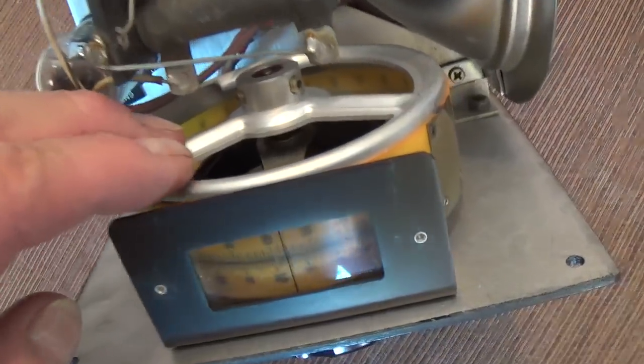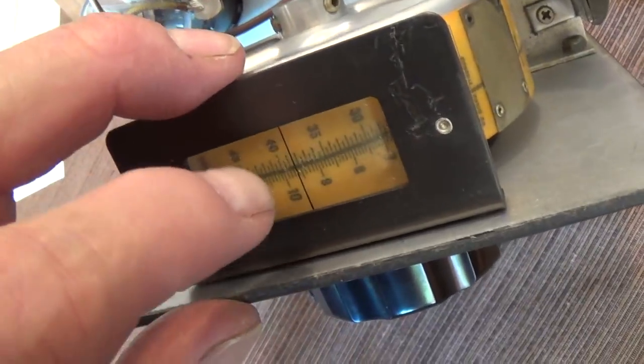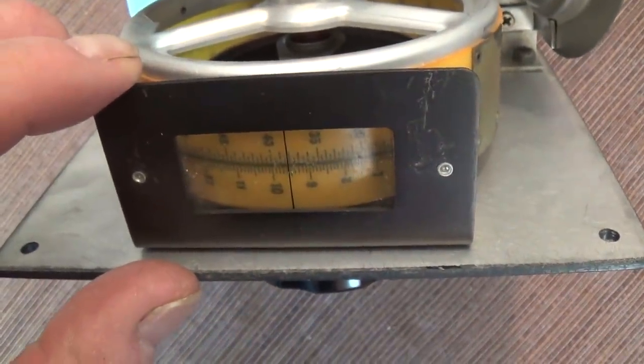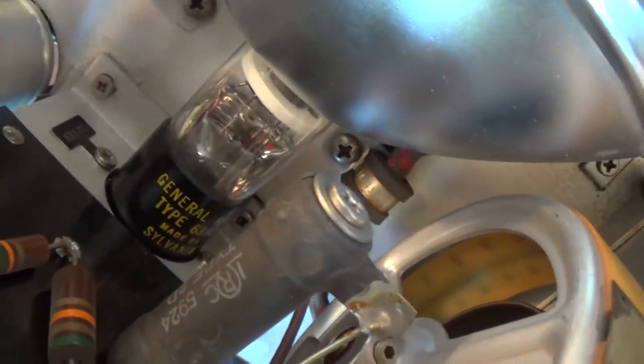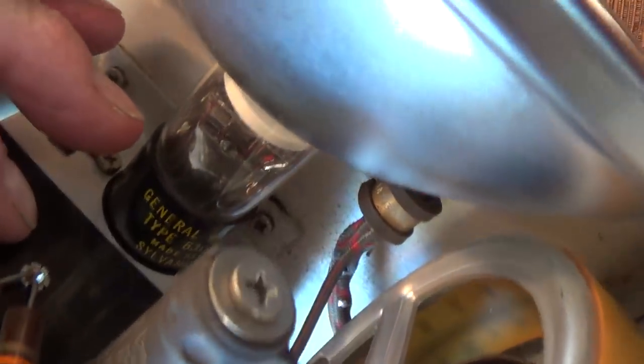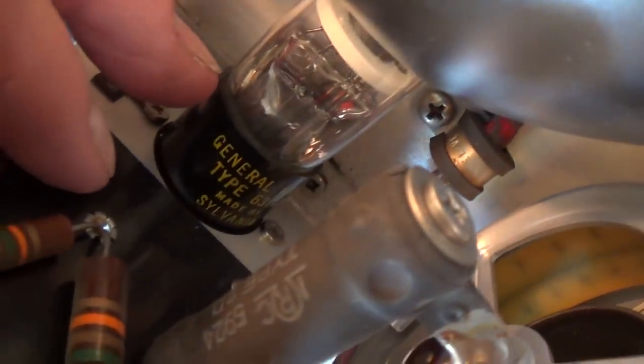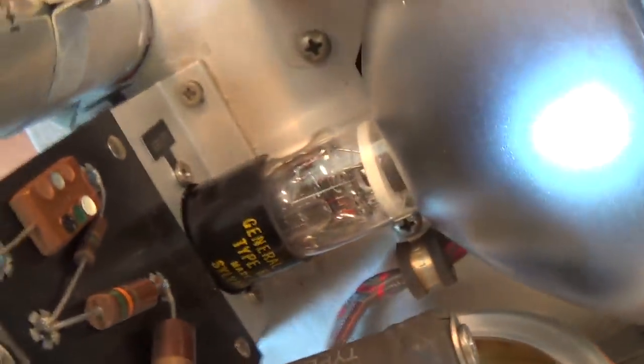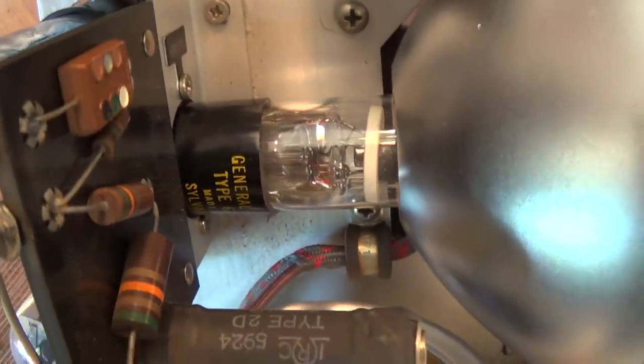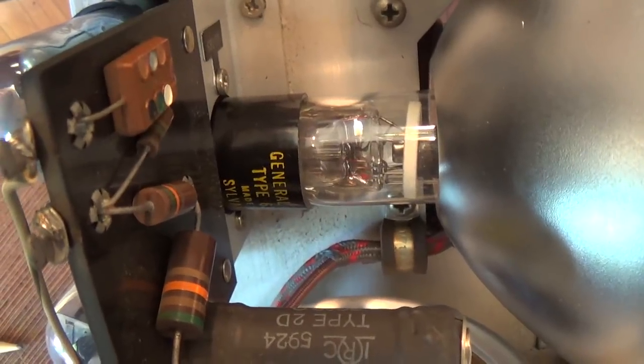Now looking down from above, we can see our speed readout wheel with its 2 ranges, high and low. And then way back underneath here, we can see that little Mazda 6-volt bulb that will illuminate the readings so we can see them in the dark. Next, we'll come over here to the rear 2/3 of that 631 strobe tube. It says General Radio Type 631, made by Sylvania. God only knows what those cost. I'm sure it's more now than it was back then.